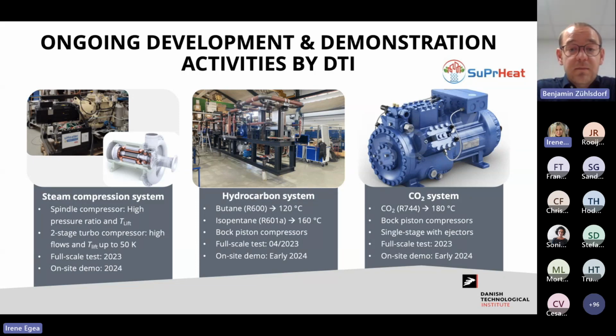The hydrocarbon system is also part of the SuPrHeat project here. It's a 2-stage or cascade system, butane up to 120 degrees, isopentane up to 160 degrees. We are testing it actually here. It's in our laboratory today, and we are soon starting it up. And then we're building also a CO2 system, also at 500 kilowatts. This will also be tested here by the end of the year. We're currently in the detailed design, ordered first components. So we will also have the full-scale testing here.